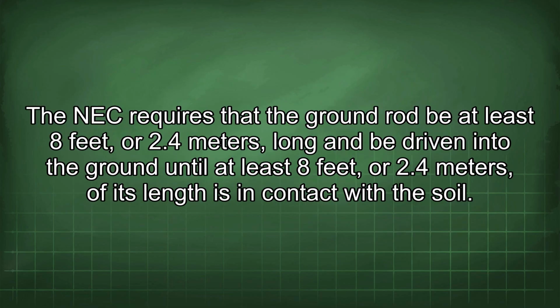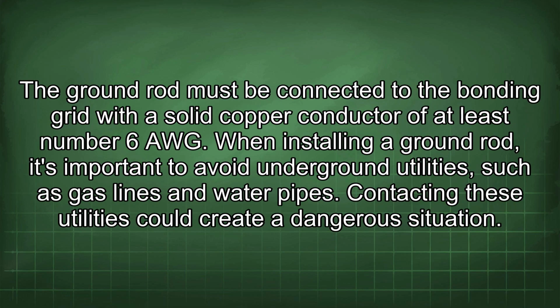The NEC requires that the ground rod be at least 8 feet or 2.4 meters long and be driven into the ground until at least 8 feet or 2.4 meters of its length is in contact with the soil. The ground rod must be connected to the bonding grid with a solid copper conductor of at least number 6 AWG. When installing a ground rod, it's important to avoid underground utilities such as gas lines and water pipes. Contacting these utilities could create a dangerous situation.